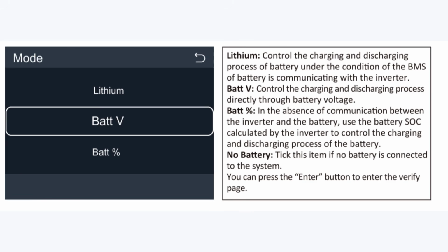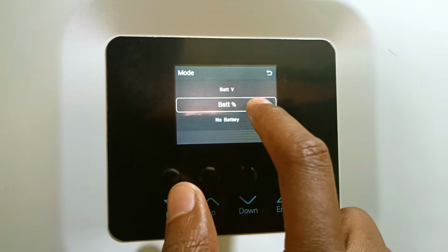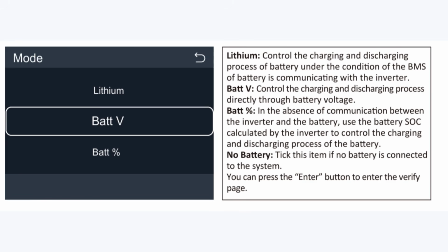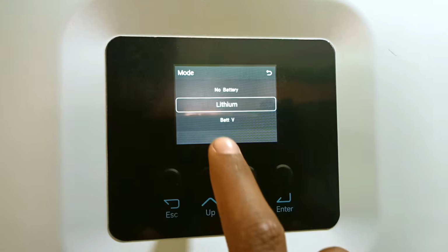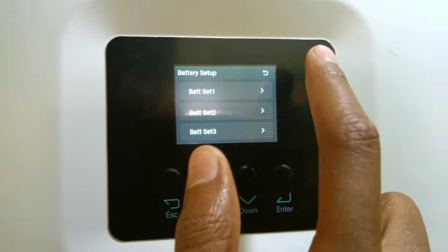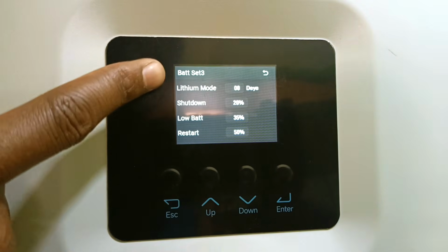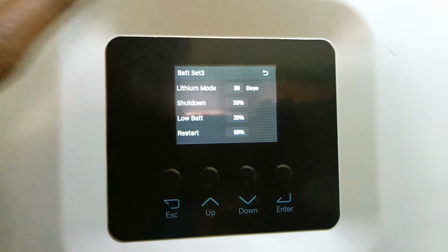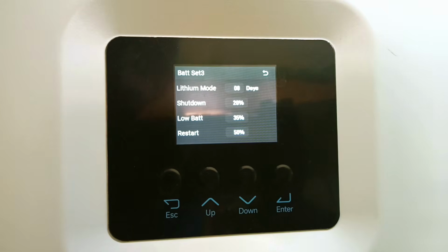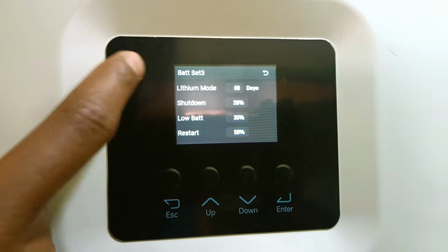Bat V: control the charging and discharging process directly through battery voltage. Battery percentage: in the absence of communication between the inverter and the battery, use the battery state of charge SOC calculated by the inverter to control the charging and discharging process of the battery. And finally, no battery: tick this item if no battery is connected to the system. You can press the enter button to enter the verify page. I selected lithium, and since I have selected lithium in battery set 3 here, you can see that the 00 at the top means that the inverter and the battery are communicating with each other. I just left everything else as it is here.